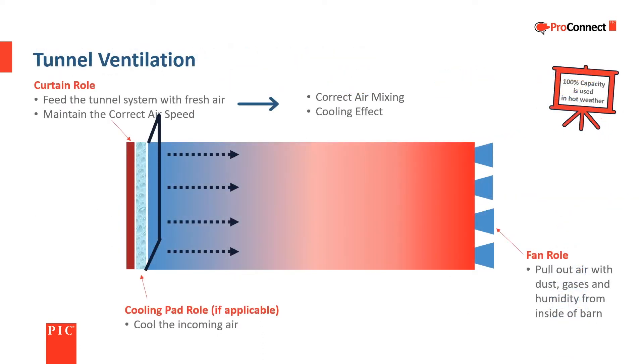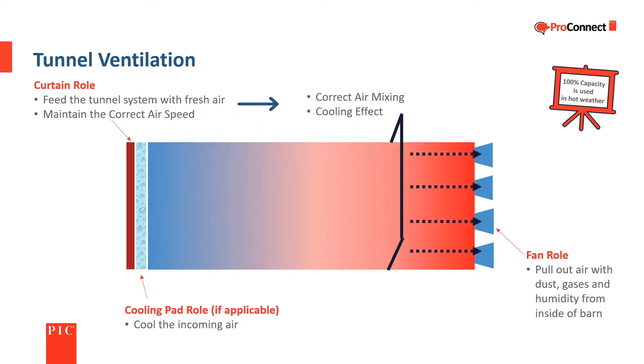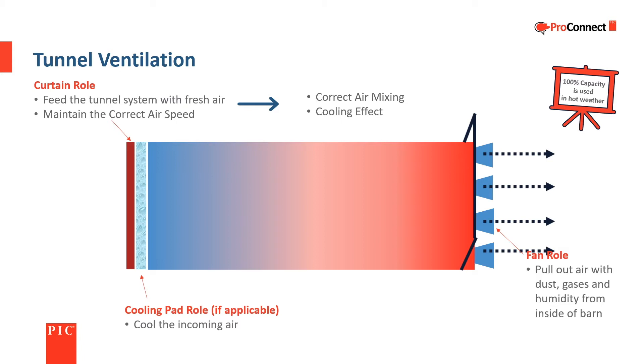Many barn designs use ceiling inlets during cooler weather and tunnel ventilation during hot weather. Tunnel ventilation moves a larger amount of air through the building and creates higher air speed at the pig level to provide additional cooling effect. The fans pull out the dust, gases, and humidity. A curtain at the opposite end of the barn from the fans raises and lowers to regulate the air speed entering the barn, which helps maintain the correct air mixing and cooling effect. An evaporative cooling pad may be used to cool the incoming air.